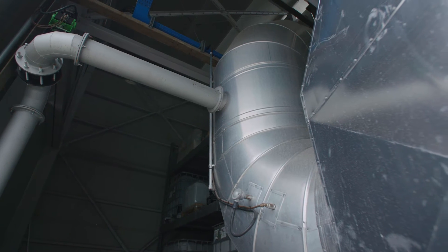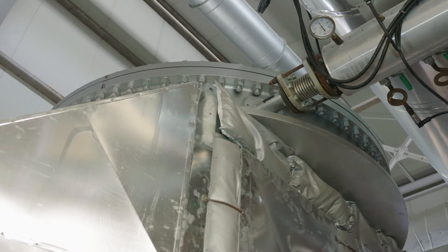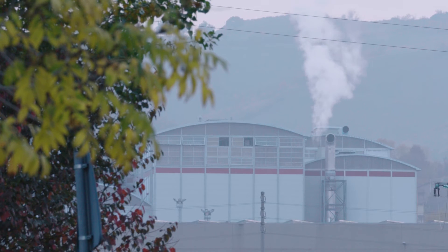Designing such a unit with exhaust flue gases is an engineering challenge. The exhaust stream straight from the kilns contains both hydrofluoric acid and particulate, and has high temperatures and flow rates that could possibly damage the system. So the engineers had to find the right setup and select the right materials for the heat pipes so that thermal recovery would work efficiently inside the plant's environment and within the temperature range applied.